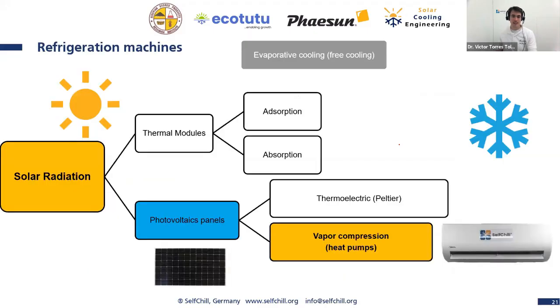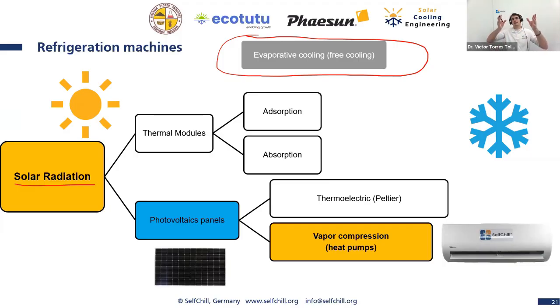So we are coming closer, but that's not the only way of doing solar cooling. If we consider that we have solar radiation and we want to use it for cooling, I have to tell you before going here, you might like to consider evaporative cooling, which is even free of energy. This means you have a material that is wet, and because water is evaporating, you have a cooling effect. So we need to use this every time we can, especially in dry ambient conditions. You can make use of this in a very productive way. So you might have heard about evaporative coolers.